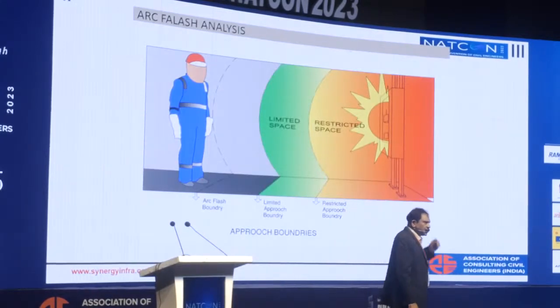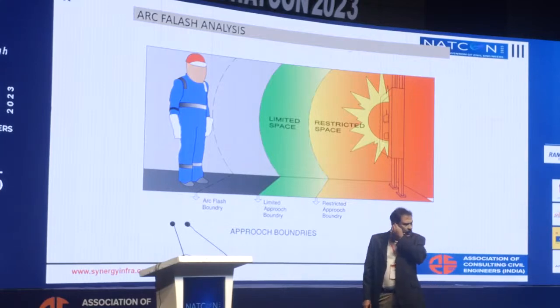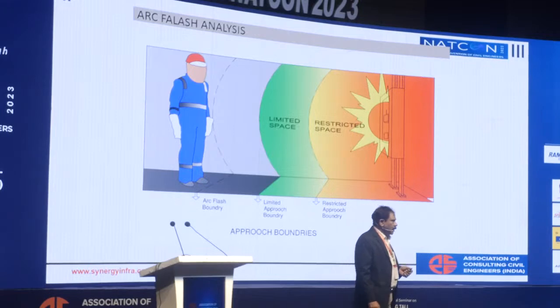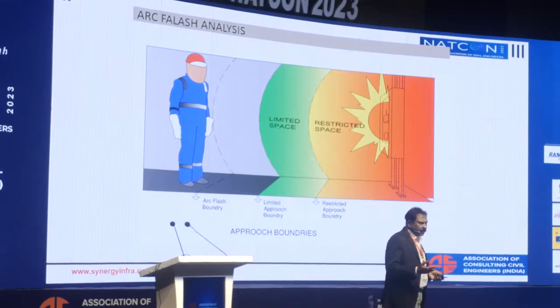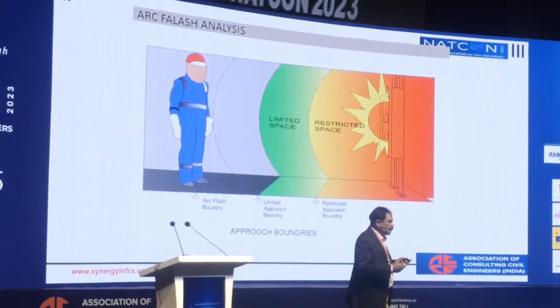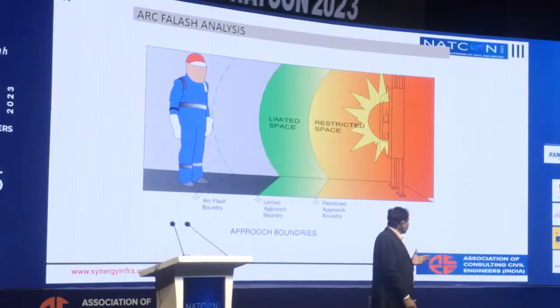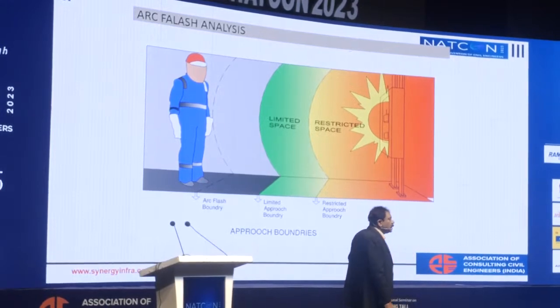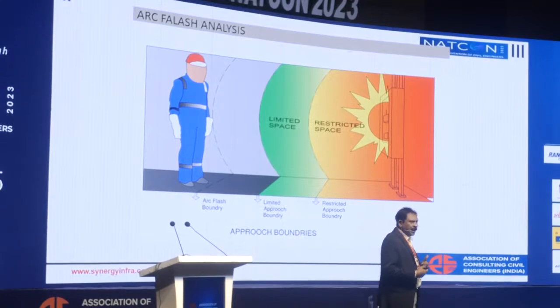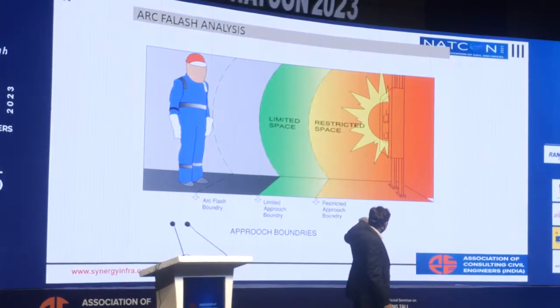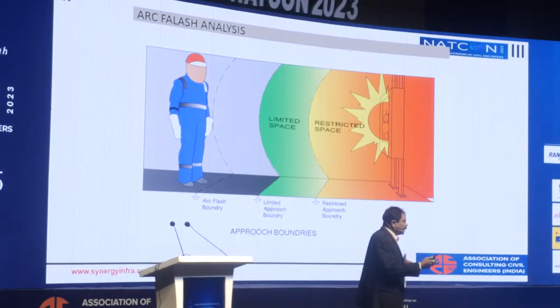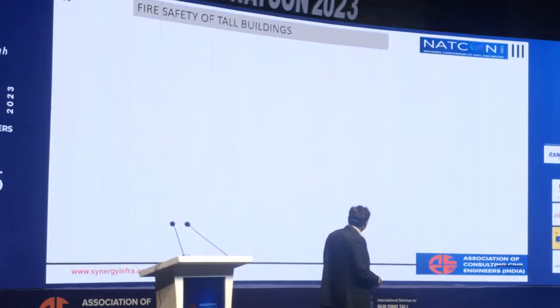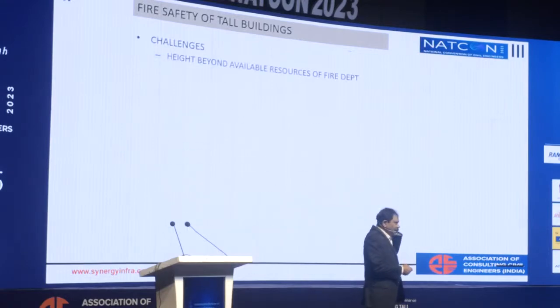One more thing introduced into the National Electrical Code 2023 is arc flash analysis. Whenever there is electrical switchgear, there is a possibility of an arc flash or arc blast. For the operators present, we are supposed to do this kind of analysis to see what kind of PPE, personal protective equipment or gear, people need to wear. There should be different color codes so that a person entering a particular zone has the required PPE. This has now been specified, and we can find out the electrical energy at a particular point and then determine what kind of PPE has to be worn. So this is with respect to electrical safety.